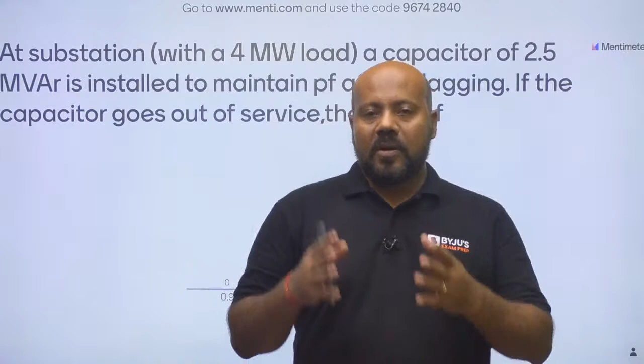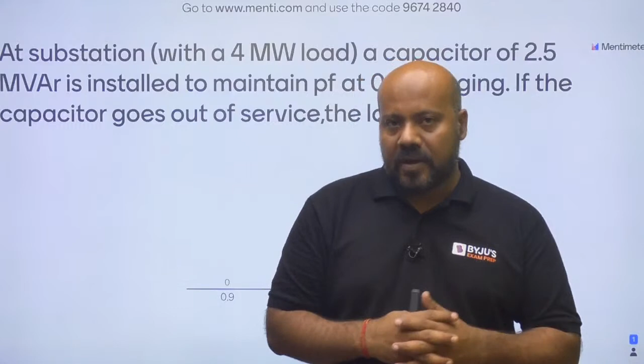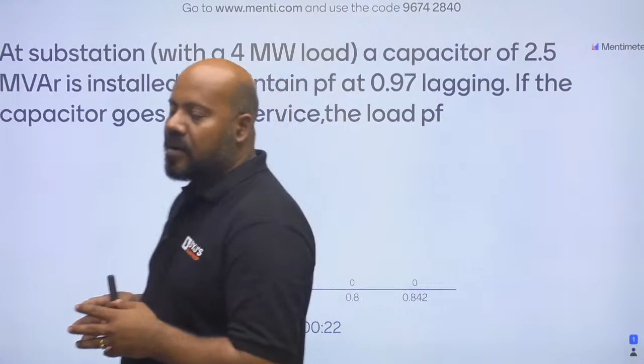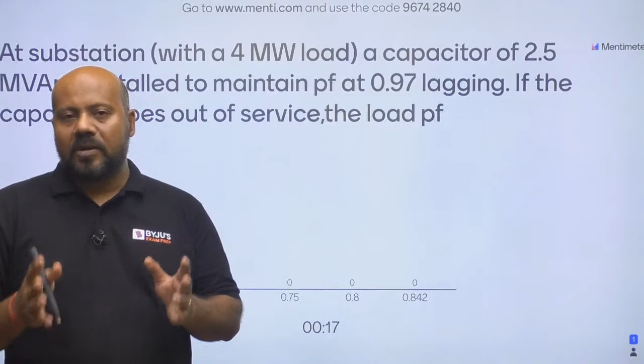Reactive power supplied by the shunt capacitor is equal to P load, that is the real power of the load, in bracket tan phi1 minus tan phi2, where phi1 and phi2 are the power factor angles for the case without shunt capacitor and with shunt capacitor. In this formula, you just need to put the values. You will get the power factor of the load when the capacitor goes out of the service.